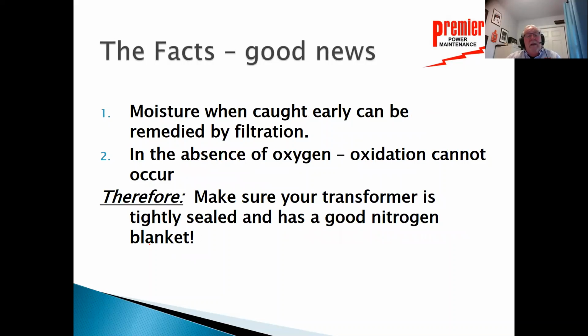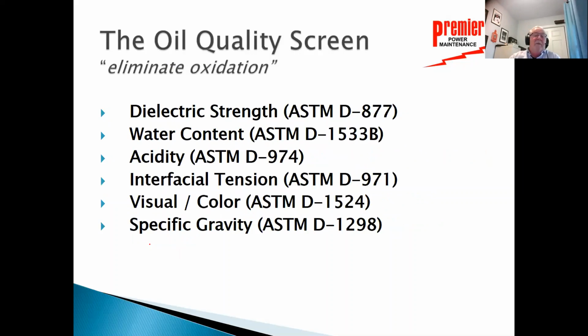Good news: if you do testing, at least annually, on your transformers and you catch the moisture early, it can be remedied by filtration. Second bit of good news: in the absence of oxygen, in other words, if you've got a good nitrogen blanket on top of that transformer and that transformer is tightly sealed, without oxygen you can't have oxidation. Therefore, make sure your transformer is tightly sealed and has that good nitrogen blanket. The whole purpose of the oil quality screen is to test the oil and make sure it is satisfactory for its intended purpose, which is to insulate and keep cool.